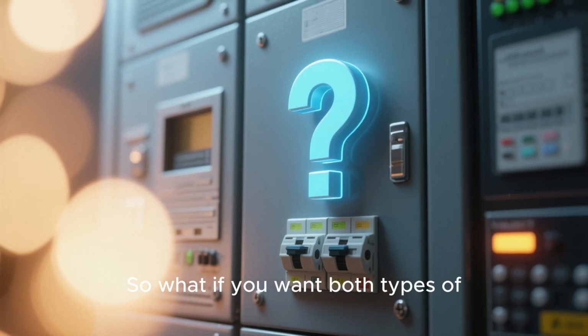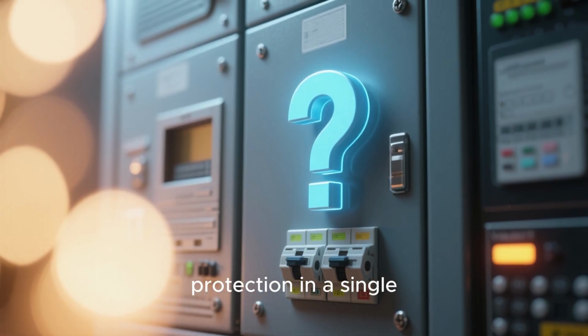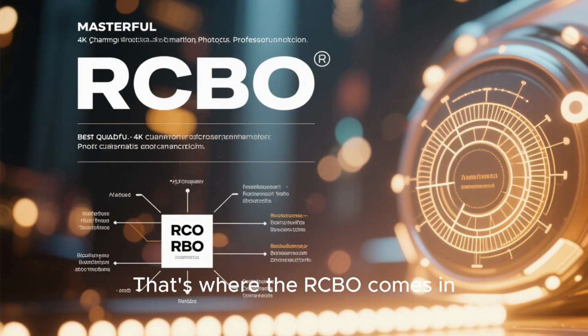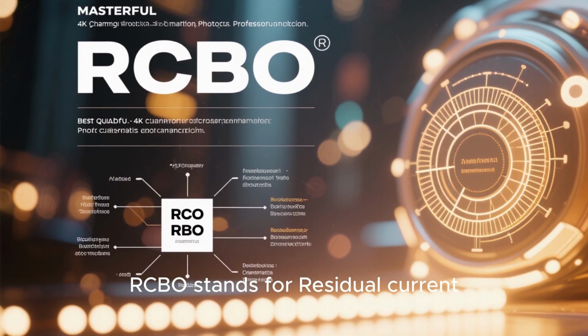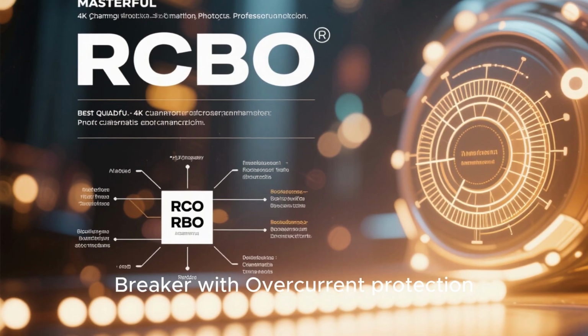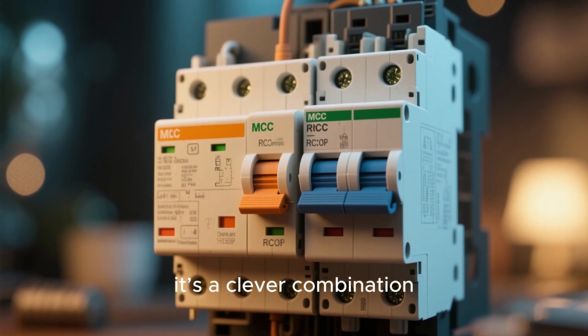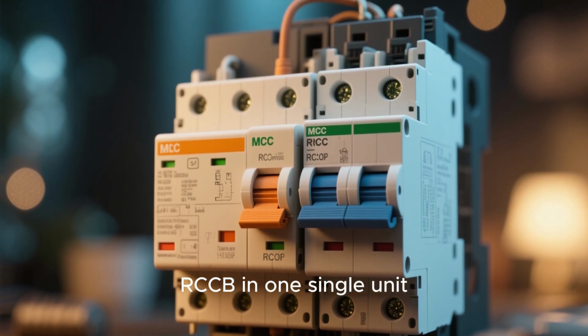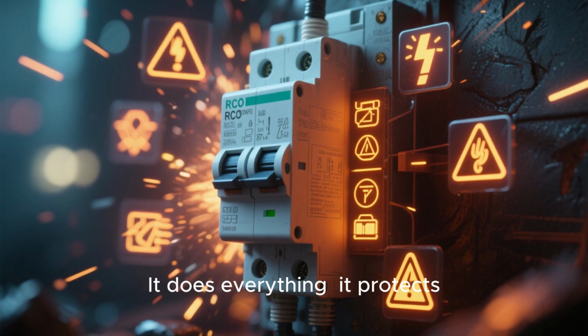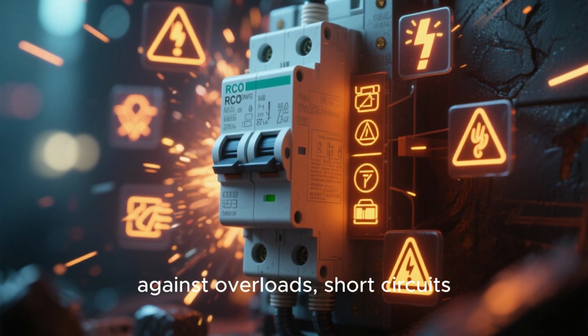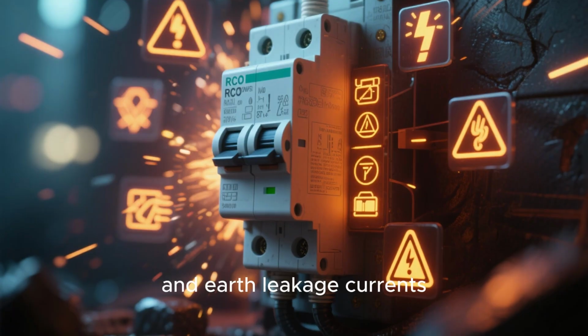So what if you want both types of protection in a single, convenient package? That's where the RCBO comes in. RCBO stands for Residual Current Circuit Breaker with Overcurrent Protection. As the name suggests, it's a clever combination of an MCB and an RCCB in one single unit. It does everything. It protects against overloads, short circuits, and earth leakage currents. This makes it an all-in-one safety device.